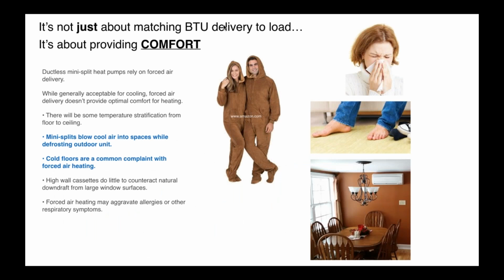Okay. Ductless mini splits. Any air source heat pump has to have a defrost in a cold climate. With a ductless mini split, you're pulling heat, literally, you're pulling heat out of the room where those cassette units are mounted to melt the frost in the outdoor unit. You're blowing cold air into the room to do that.